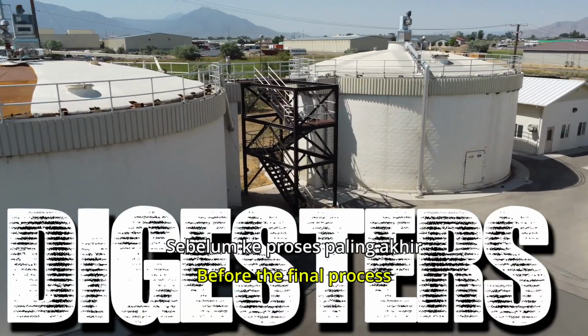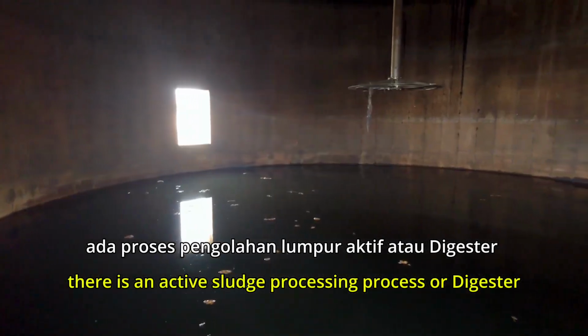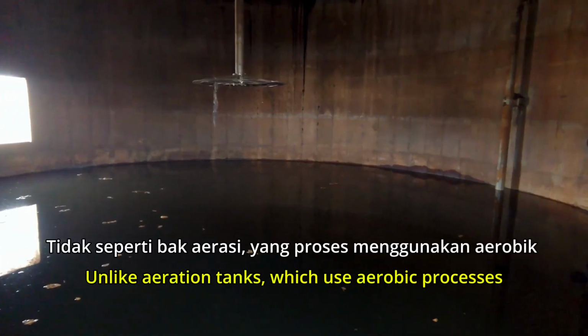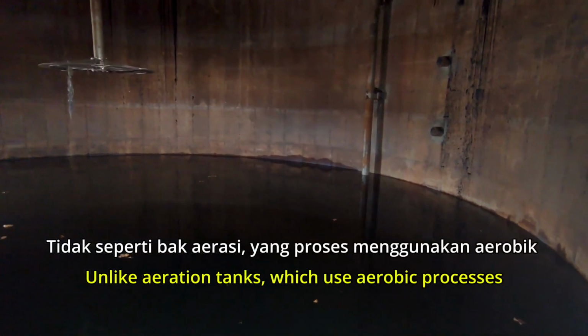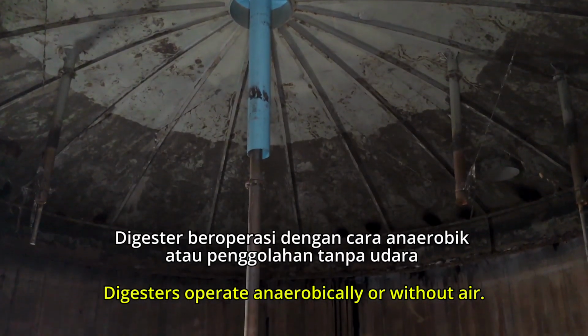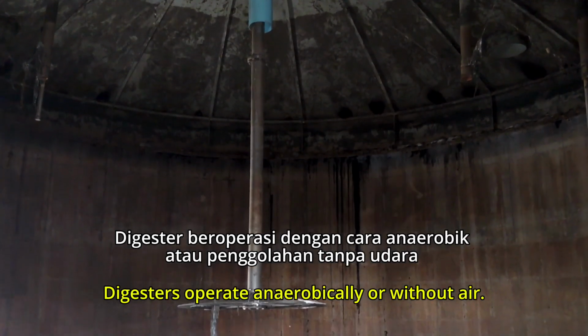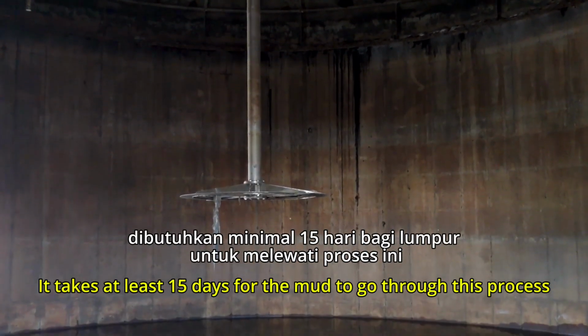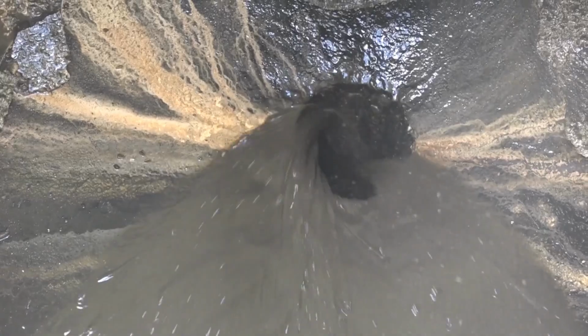Before the final process, there is an activated sludge processing process, or digester. Unlike aeration tanks, which use aerobic processes, digesters operate anaerobically, or without air. It takes at least 15 days for the mud to go through this process.